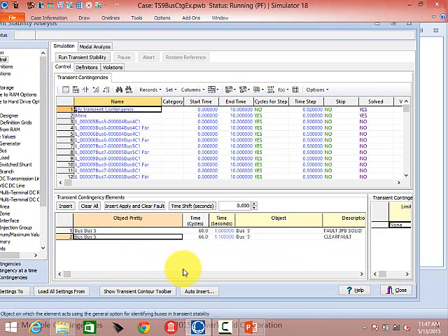When you do the fault, clear the fault, before the next contingency, you're running the initial state. There's nothing in there to define to say restore initial state. Right. The user does not have to restore an initial state. The software handles that. Once you start the transient run, that's the initial state, and then it returns back to that in between each individual contingency. So you don't have to worry about that.